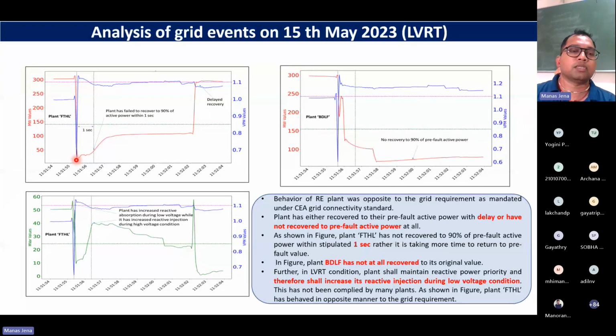But the next requirement was that you should be able to recover 90% of your pre-fault generation within 1 second. This is the 1 second time instant. You can see a very sluggish response. The plant has failed to recover to 90% of the active power within 1 second. This is not what was desired. That is the first thing. Next, this plant. So this is plant FTHL. This is some other plant, BDLF.